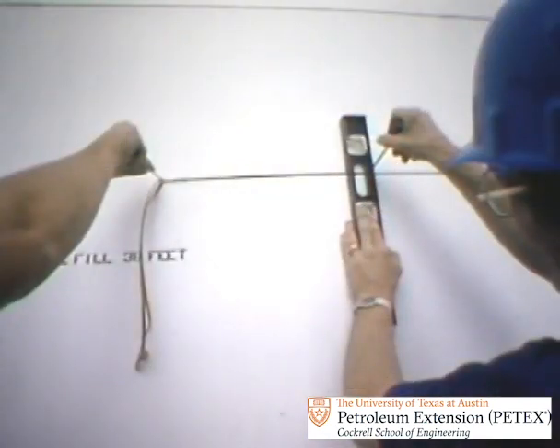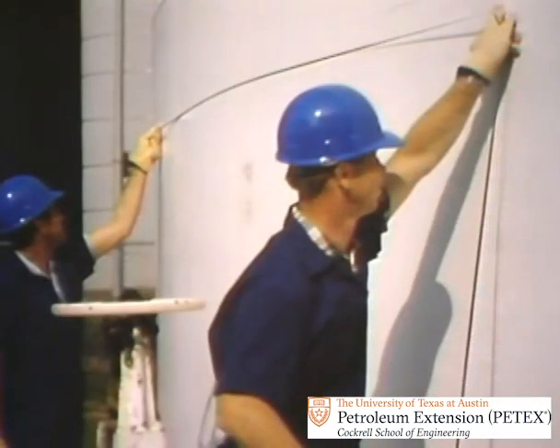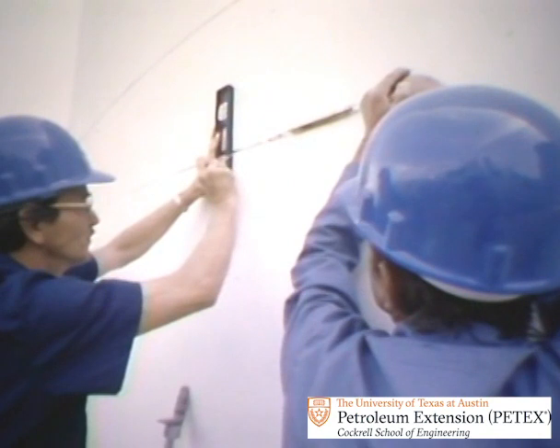To measure the circumference of the bottom ring with the standard tape, the crew anchors the tape and scores the tank at the 0 reading on the tape. They then extend the tape on the shell, being certain it stays on the path marks. Required tension, read from the tape's NBS report, is pulled, and a vertical score is made on the shell at the 100-foot tape reading.